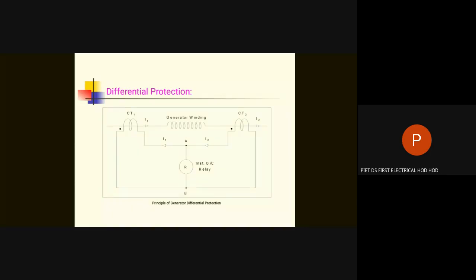The principle is very simple: the primary currents, capital I1 and capital I2 as they are shown, flow through the generator winding. I1 is on the neutral side, I2 is on the line side. They have the same magnitude if there is no internal fault. That means if there is an external fault, or if the rated condition is there, I1 and I2 are the same. So small I1 and small I2 flow in the pilots. The wires which are connected in the secondary of the CT are known as pilot wires. The current I1 and I2 flowing through the pilot wires is the same. Therefore, I1 minus I2 flowing through the instantaneous overcurrent relay is 0, and therefore no protective scheme will operate.